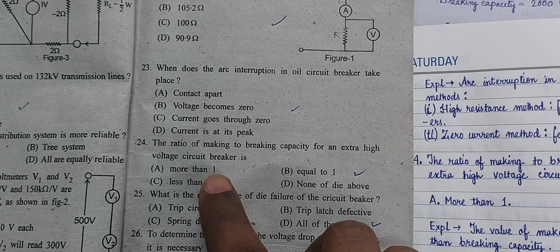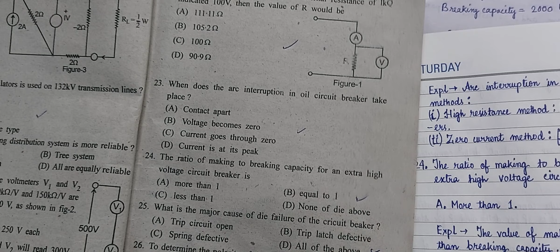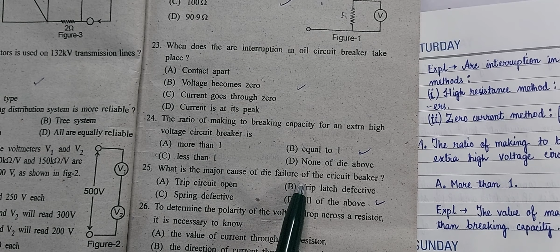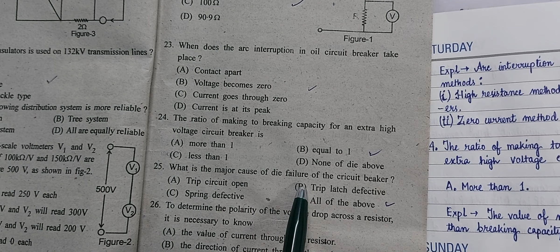Now the ratio of making to breaking capacity of an extra high voltage circuit breaker is always more than 1, because making capacity means breaking capacity into 2.55. This is the relation you should know. Therefore, making capacity is always greater than breaking capacity. So the ratio of making to breaking capacity should always be more than 1. Question number 25. What is the major cause of the failure of the circuit breaker? Trip circuit open, trip latch defective, spring defective. These all are the causes of the failure of circuit breakers.